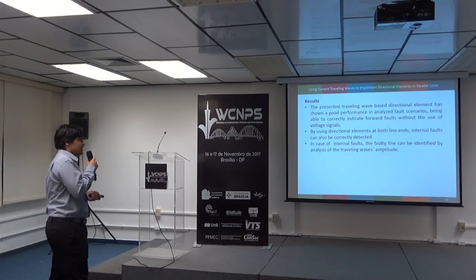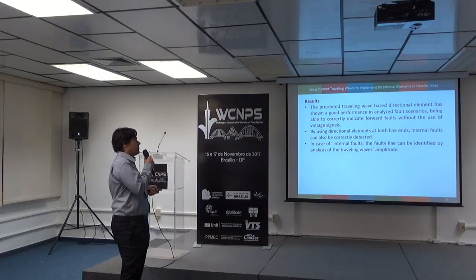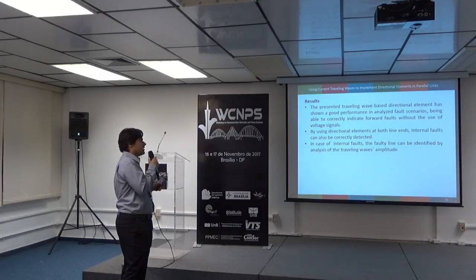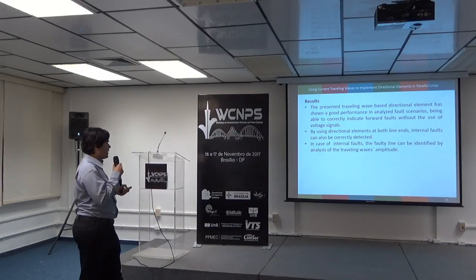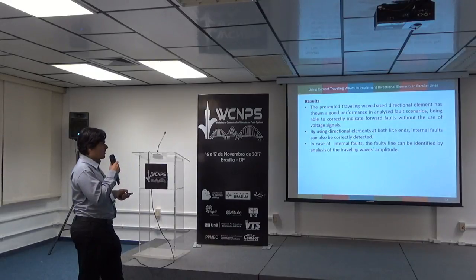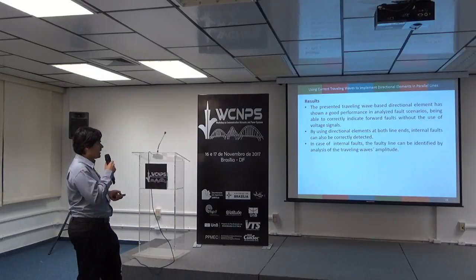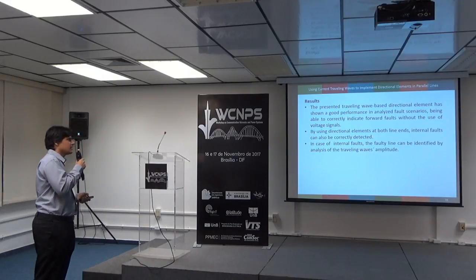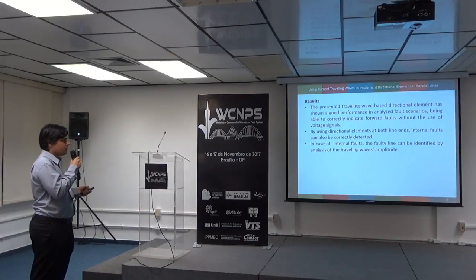Results. The presented traveling wave-based directional element has shown a good performance in analyzing fault scenarios, being able to correctly indicate forward faults without the use of voltage signals. By using directional elements at both line ends, internal faults can also be correctly identified. In case of internal faults, the fault line can be identified by analysis of traveling waves amplitude.